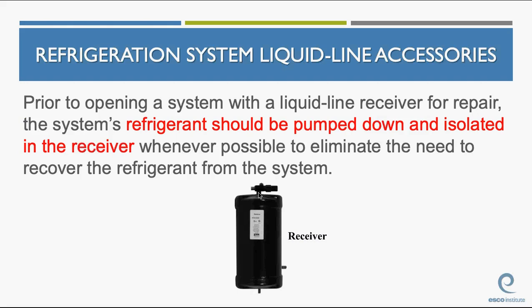Okay, and I could just valve it off, run the compressor until my suction line is down below 0, and I have all of my refrigerant caught between the receiver and the compressor. In other words, liquid refrigerant all the way back from the receiver. Any questions on that?